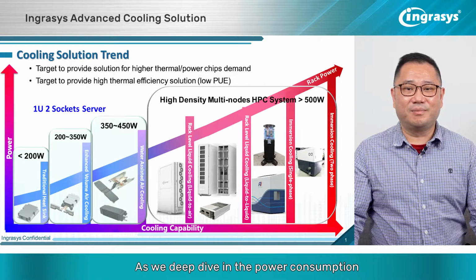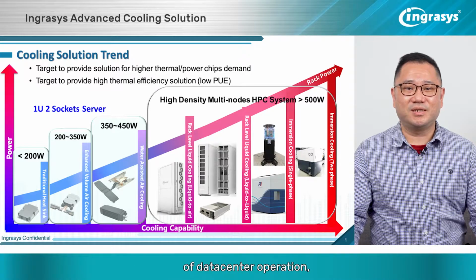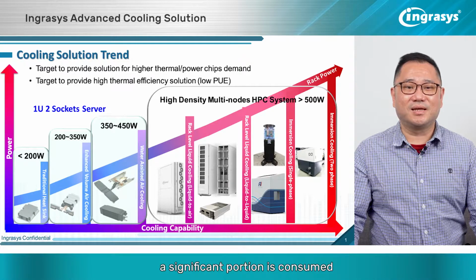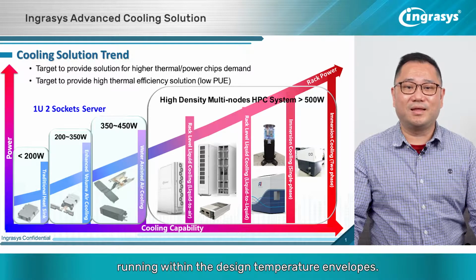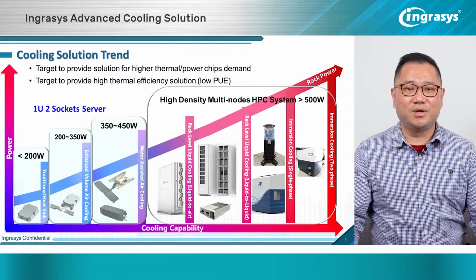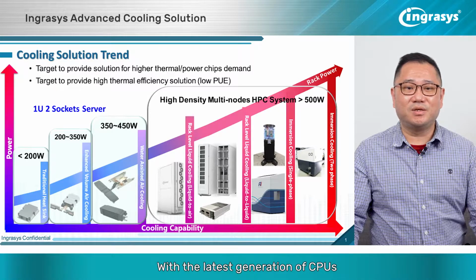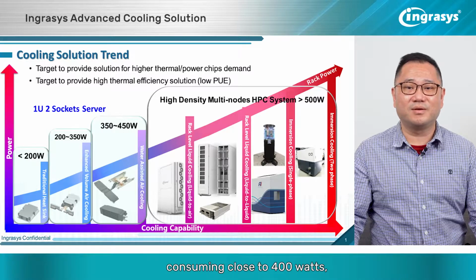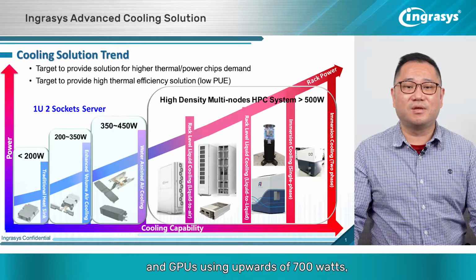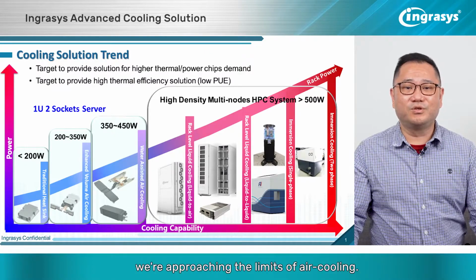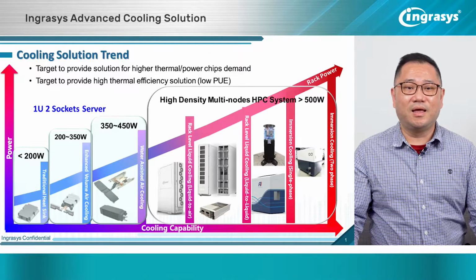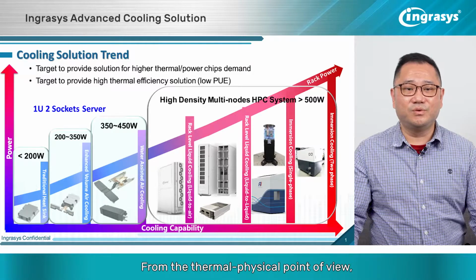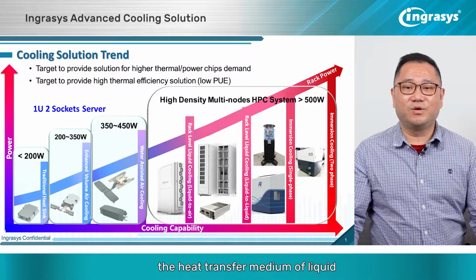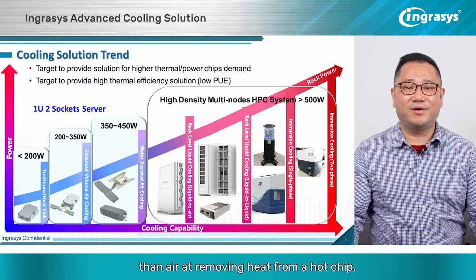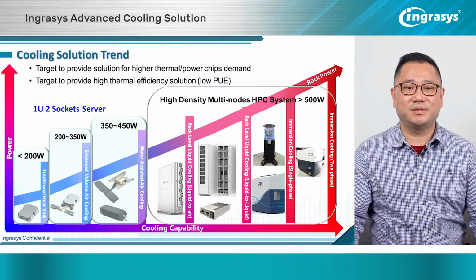As we deep dive into the power consumption of data center operation, a significant portion is consumed by the cooling systems used to keep the systems running within the design temperature envelopes. With the latest generation of CPUs consuming close to 400 watts and GPUs using upwards of 700 watts, we are approaching the limits of air cooling. From the thermal-physical point of view, the heat transfer medium of liquid is much more effective than air at removing heat from a hot chip.